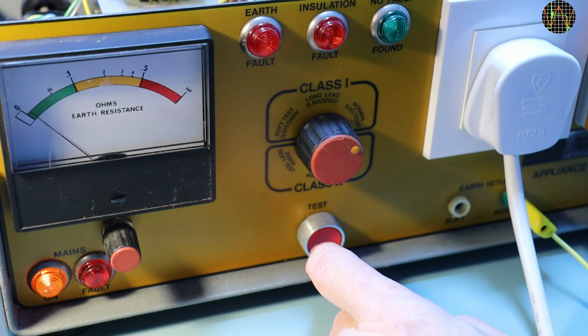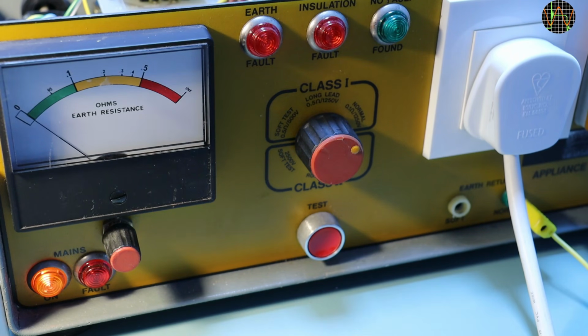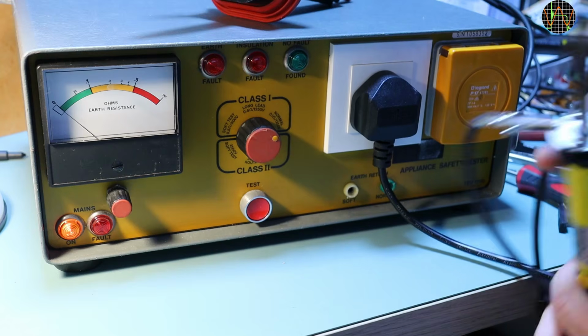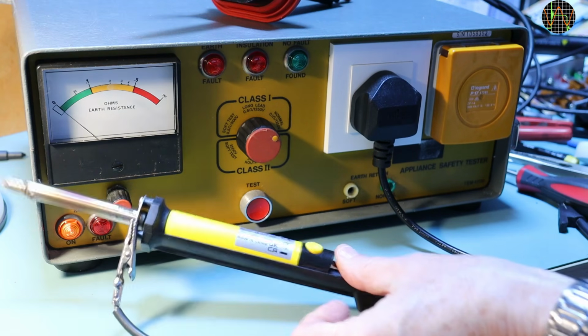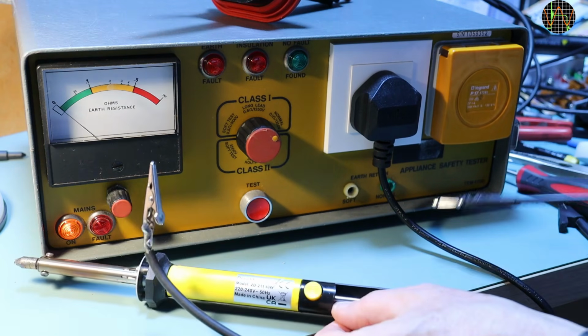From the early adjustment, this behavior means it's hard at the threshold, which is okay for 0.1 ohm. Well, I think this will have to do. I can't adjust it any better. I closed the unit back up and I thought I might actually do a real class 1 test.